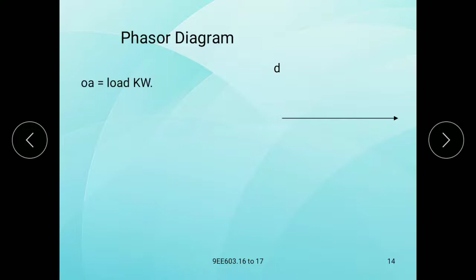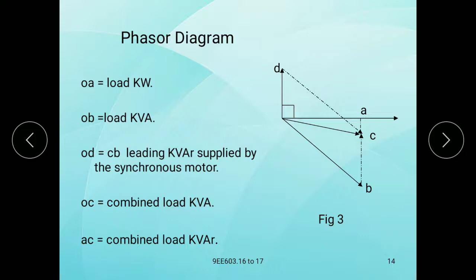Here, observe the phasor diagram. OA is equal to load KW. The x-axis is always taken as KW, and the y-axis, upward or downward, is taken as KVAR. So OB is load KVA, and OD is equal to CB, the leading KVAR supplied by the synchronous motor. OC is the combined load KVA. AC is equal to the combined load KVAR.